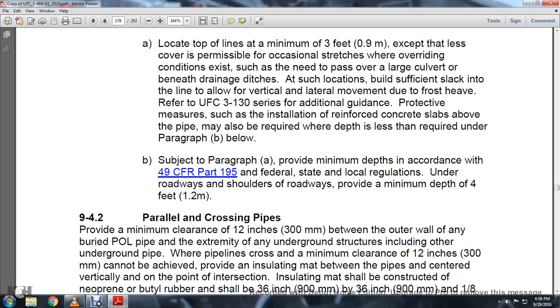9.4.2 Parallel and crossing pipes. Provide a minimum clearance of 12 inches between the outer wall of any buried petroleum, oil, and lubricant pipes and any other underground structures, including underground pipes. Where pipelines cross and the minimum clearance of 12 inches cannot be achieved, provide an insulation mat between the pipes, centered vertically on the point of intersection. The insulation mat should be constructed of neoprene or rubber and shall be at least 36 inches by 36 inches by 1/8 inch thick. Provide a test station with two test wire leads with each pipe.